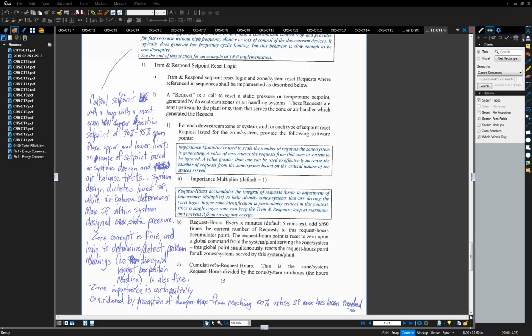And then go out and look at, maybe it's a damper that's stuck. I've actually seen insulation going into the inlet side of a VAV box. Again, many times when we look at the high request hours and go out there, somebody's dumped a whole bunch of equipment in there and not rebalanced the system or put in a larger box or anything like that. So one of the things that's nice about trim and respond as opposed to doing it as a PI loop is it gives you feedback on the demanding zones. And it makes it much easier from a facility side to go and fix them. Yeah, and that makes sense.